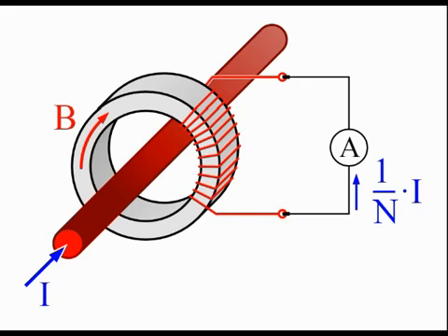Typically, current transformers consist of a silicon steel ring core wound with many turns of copper wire as shown in the right illustration. The conductor carrying the primary current is then passed through the ring. The CT's primary therefore consists of a single turn. The primary winding may be a permanent part of the current transformer, with a heavy copper bar to carry current through the core. Window-type current transformers, aka zero-sequence current transformers, or ZSCT, are also common, which can have circuit cables run through the middle of an opening in the core to provide a single-turn primary winding. To assist accuracy, the primary conductor should be central in the aperture.